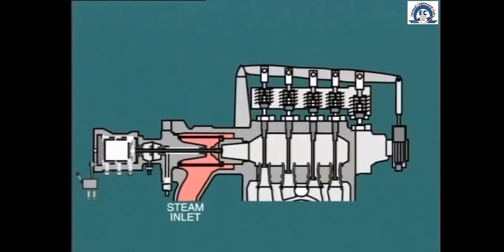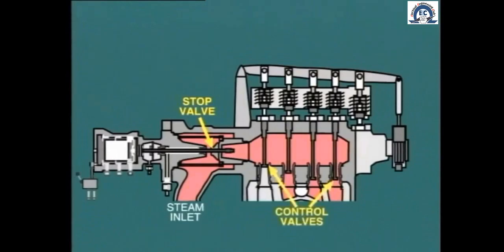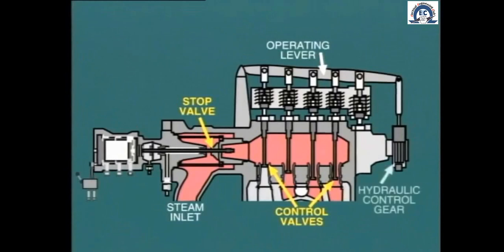In most arrangements of this type, a stop valve is fitted at the entrance to each steam chest. During normal operation, the stop valve remains in the wide-open position, while the control valves are modulated to adjust steam flow. The actual opening of the control valves is determined by the position of the operating lever, and this in turn is adjusted by the power cylinder of the hydraulic control gear.